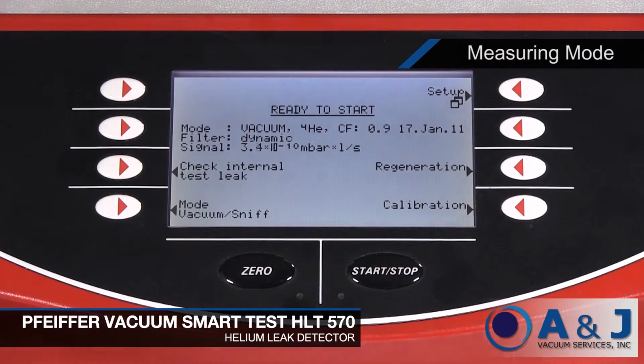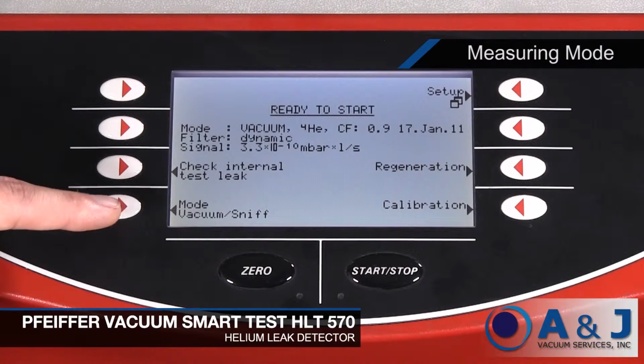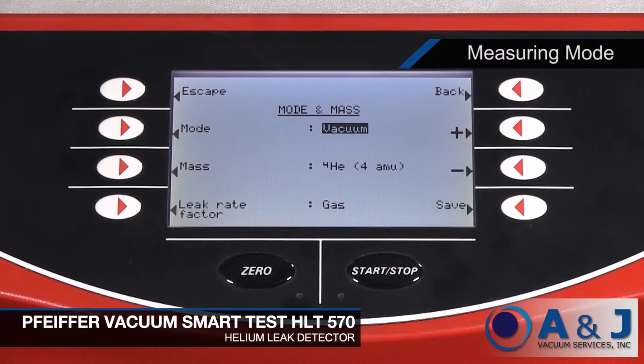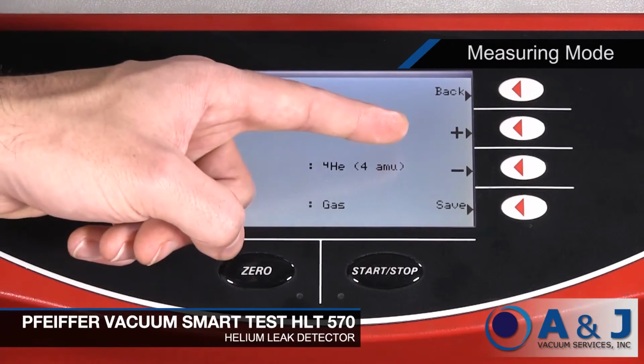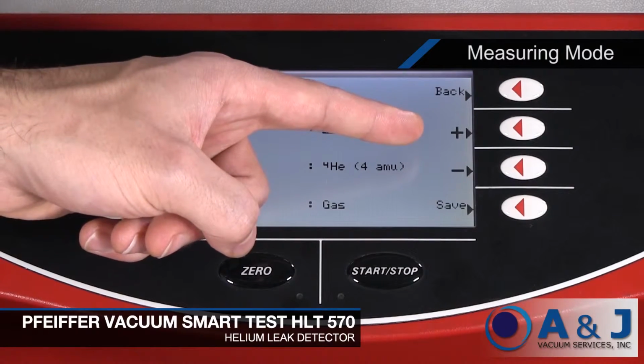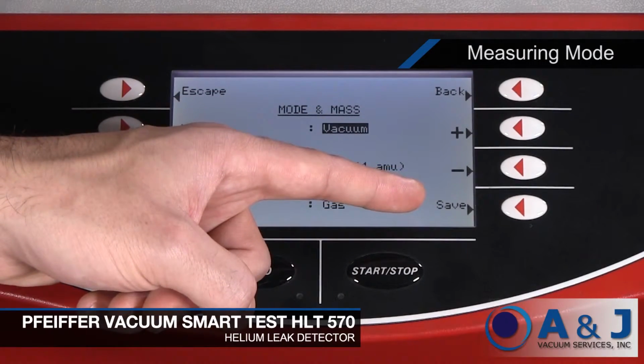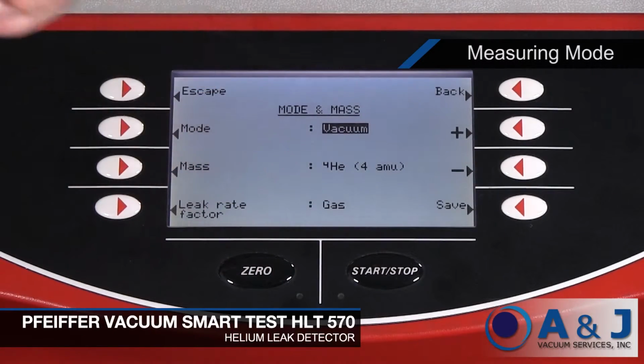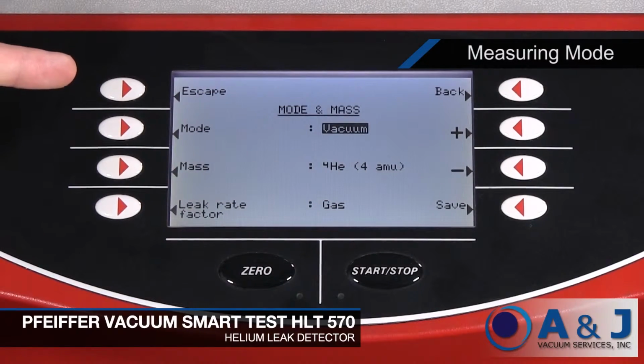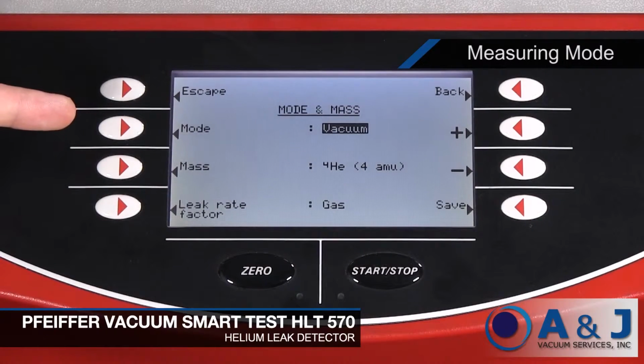The Pfeiffer HLT 570 has 2 measuring modes. To change the setting, press Mode Vacuum/Sniff. Select the desired option with the soft keys on the right and left of the screen. You can change the value with the plus and minus keys. Prolonged pressing causes the parameters to be run through automatically. You can save the new value with the Save key, or go back 1 level with Back, or to the measured value or Ready to Start display with the Escape key. The Mode option allows you to select vacuum mode or sniffing mode. You also have the option for mass and leak rate factor.